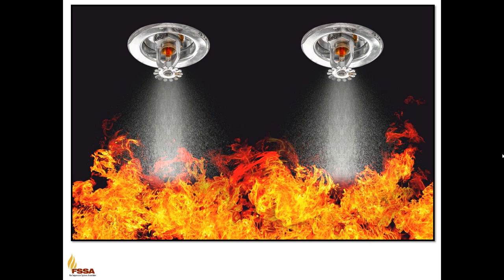It is important to understand their purpose. The sprinkler heads that you see above you in every building are heat activated. Contrary to Hollywood's many inaccuracies, they do not all activate at once in normal applications. A single sprinkler head will fuse or open when enough heat is created beneath it. That particular sprinkler head will then continue to discharge water at a rate of roughly 20 gallons per minute until someone shuts off the water supply. This is simply not acceptable in data centers or other high-value applications where the water damage from a fire event could be far greater than the fire and smoke damage.